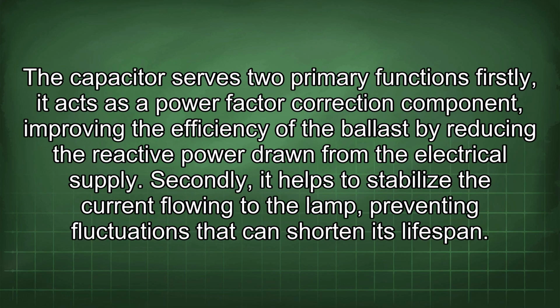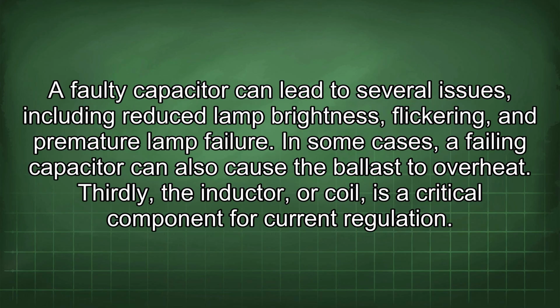The capacitor serves two primary functions. Firstly, it acts as a power factor correction component, improving the efficiency of the ballast by reducing the reactive power drawn from the electrical supply. Secondly, it helps to stabilize the current flowing to the lamp, preventing fluctuations that can shorten its lifespan. A faulty capacitor can lead to several issues, including reduced lamp brightness, flickering, and premature lamp failure. In some cases, a failing capacitor can also cause the ballast to overheat.